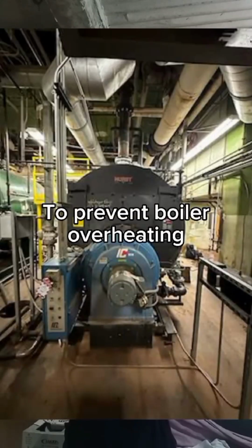To prevent boiler overheating: Number 1, test boiler water and give proper chemical treatment. Number 2, properly blow down boiler water whenever necessary. Number 3, regular cleaning of the furnace and chemical cleaning of the water side. Number 4, maintain proper boiler water level. Number 5, maintain efficient feed water pump and circulating pump. Number 6, maintain proper fuel burning process, including burner cleaning. Number 7, maintain proper function of boiler safety devices.